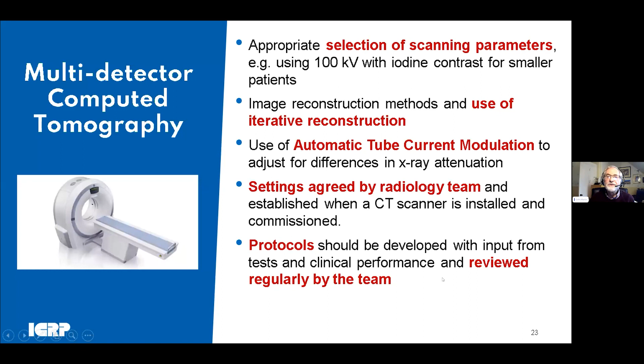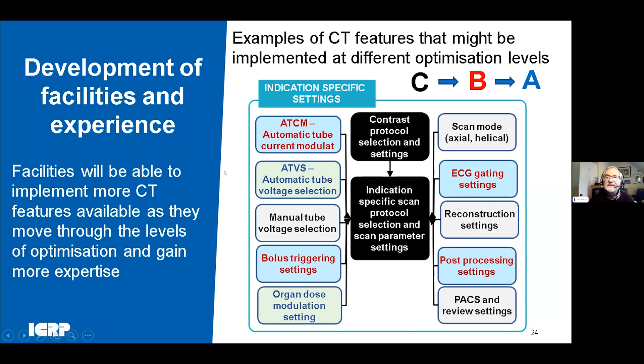So looking particularly at CT, at level C, we've got our contrast protocol settings and the indication-specific protocols. We have to have our voltage selection, the scan mode and reconstruction settings. As we move to level B, we might then fully implement automatic tube current modulation, bolus triggering, perhaps post-processing or ECG gating. And then as we move to level A, it might be that we introduce automatic tube voltage selection, organ dose modulation, things like that. So there are different things which will probably be implemented at different stages because of the level of training and expertise as the staff gradually become more experienced.